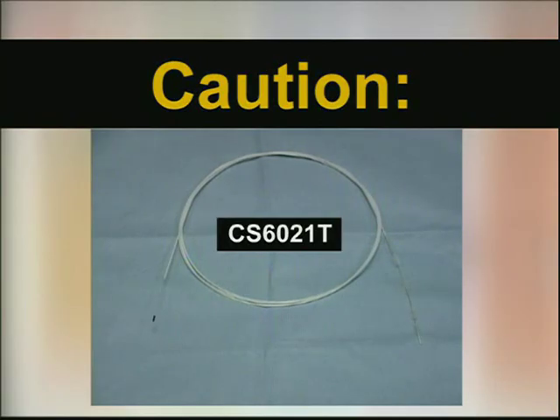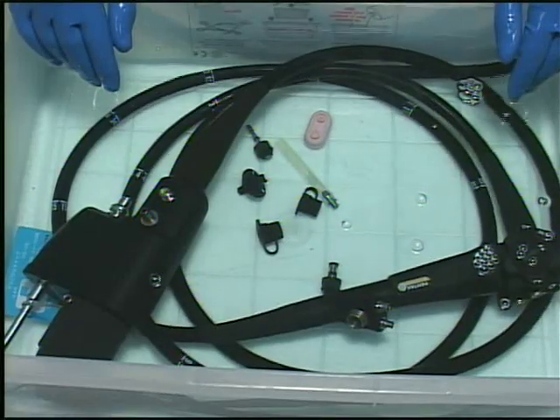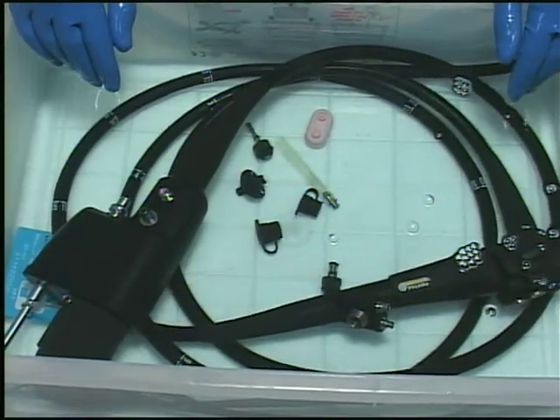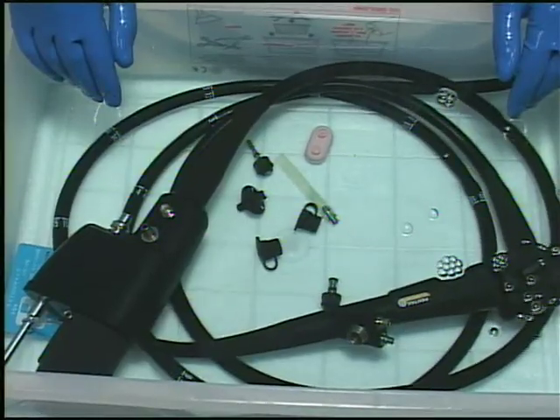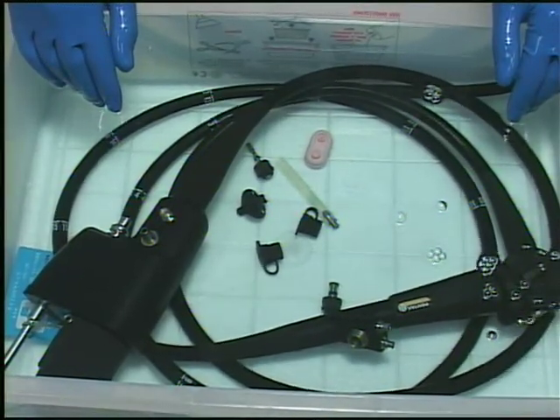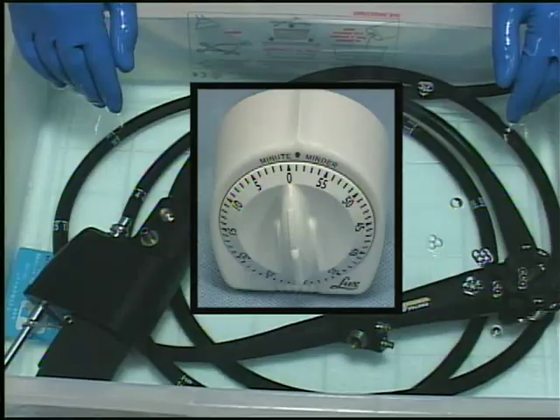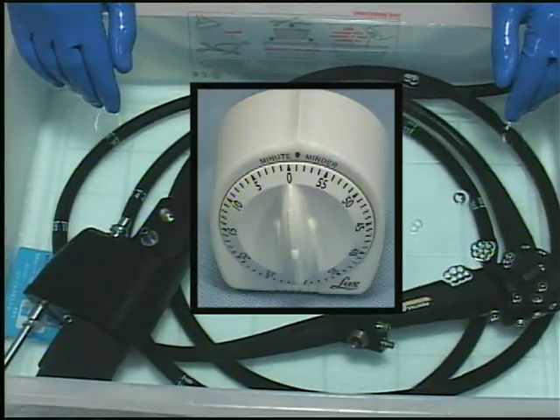Caution: the CS6021T cleaning brush is for one-time use. Never reuse the brush on more than one endoscope. The entire endoscope, including all internal channels, must then be exposed to an enzymatic cleaning solution for the time period recommended by the manufacturer of the solution.